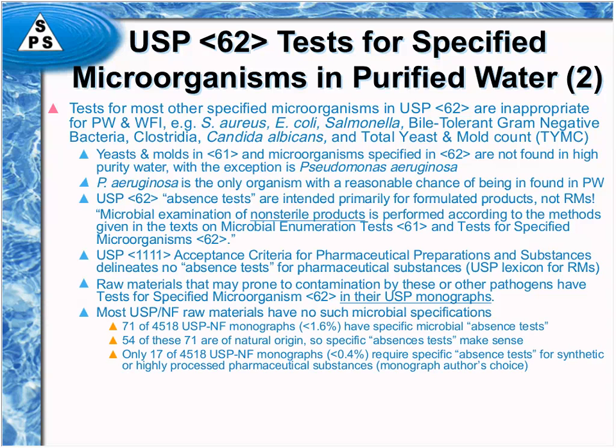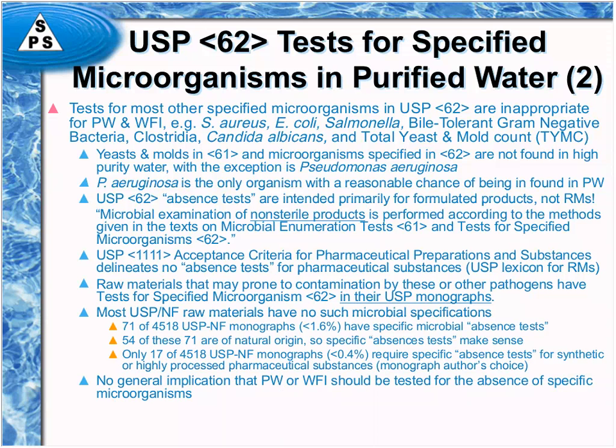Only 17 of those actually required specific absence tests for synthetic or highly processed materials. And that was because the monograph author's choice was to include them. It wasn't USP's choice. It was the monograph author's choice who submitted the text to USP. And so that obligation was carried forward. So there winds up being no general implication, really, that purified water or water for injection should ever be tested for the absence of specific microorganisms. No obligatory general requirement, okay?